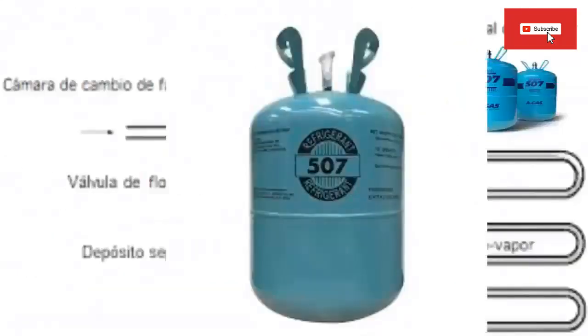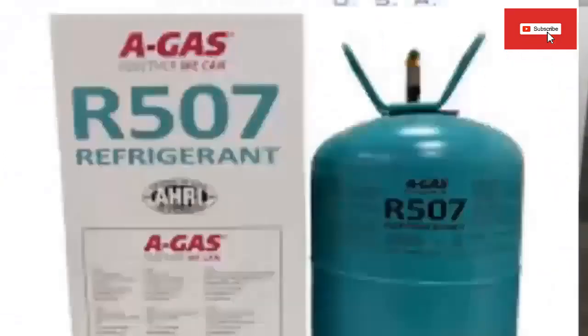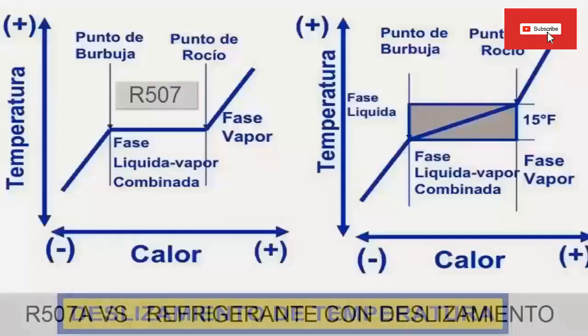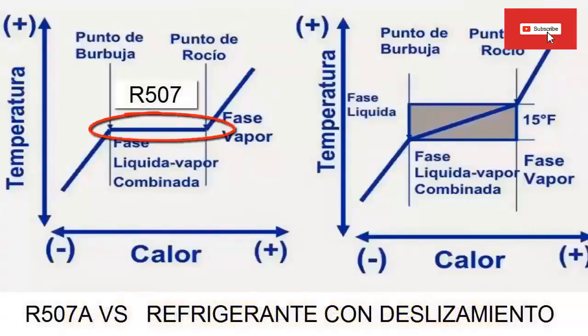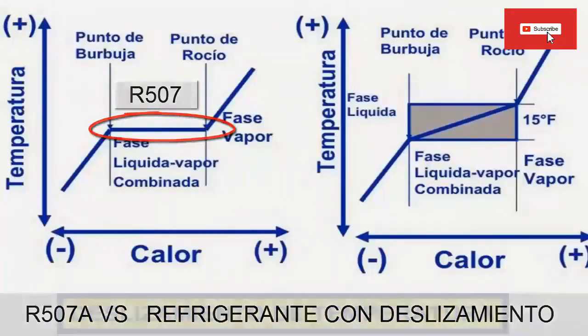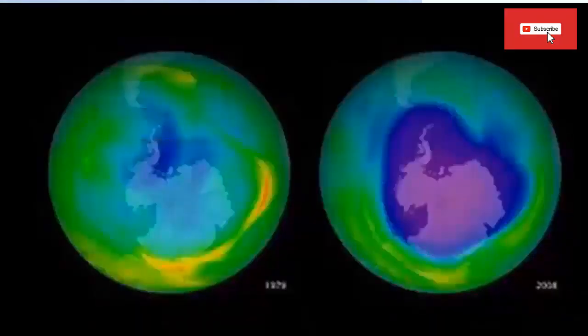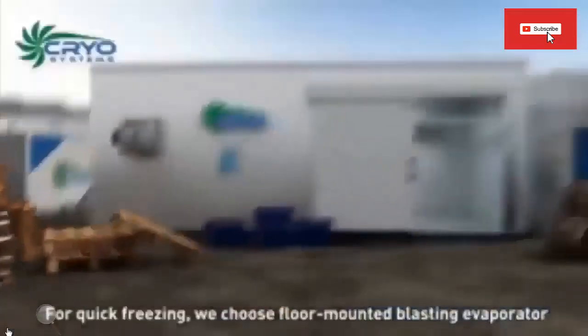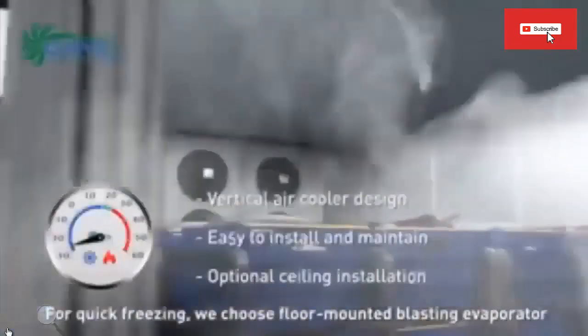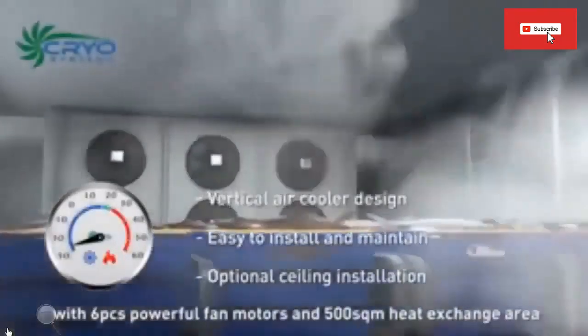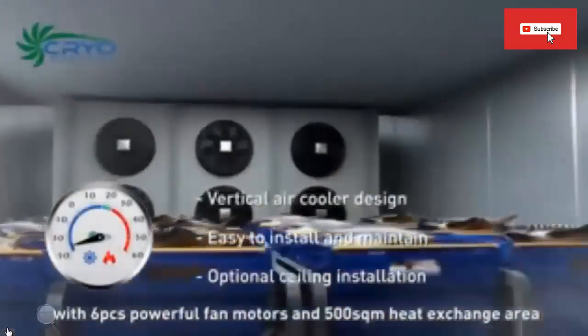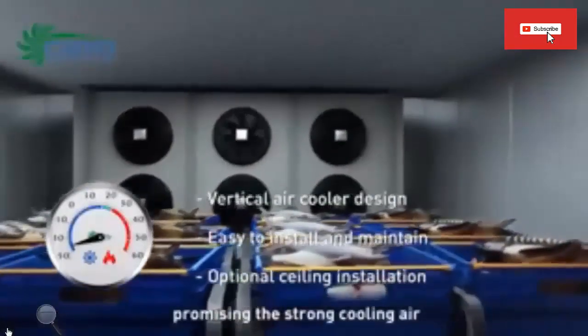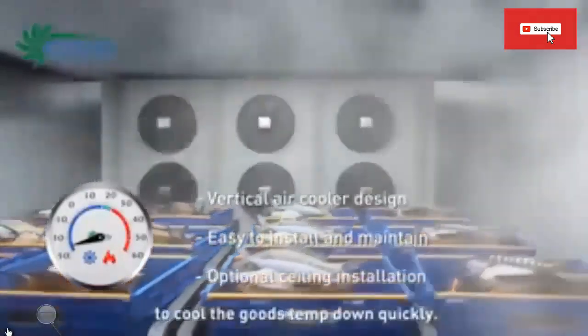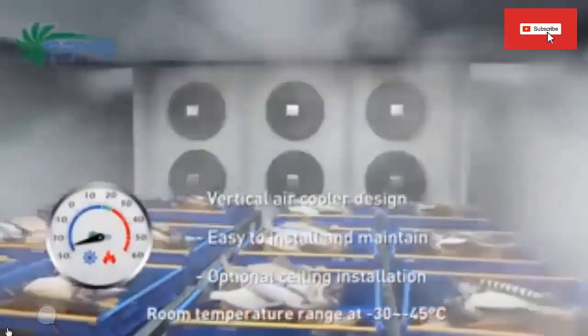The R507 refrigerant is an azeotropic mixture, that is to say, it has almost no glide. Therefore the temperature at which it is evaporating does not change if the pressure is the same. R507 has zero ozone depletion potential and similar qualities to R502 and performs well in commercial refrigeration systems used in supermarkets and was widely used in transport refrigeration. The correct lubricant for R507 is polyester oil.